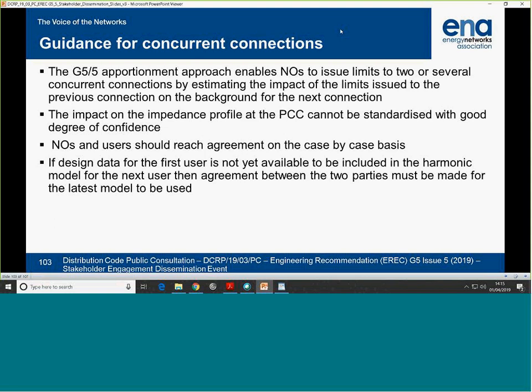I do hear your suggestion. A protection for the user connecting is that we'll do a period of measurements immediately before they connect and immediately after they connect, so we can look at the impact that they're having. If they become non-compliant, say we start exceeding the total limits in their agreements, but we can see that the measurement before was already increased, it's probably the customer before them, and they're protected against that in that measurement campaign. But finding the customer responsible and managing that is a hard task. We sort of crossed that earlier.